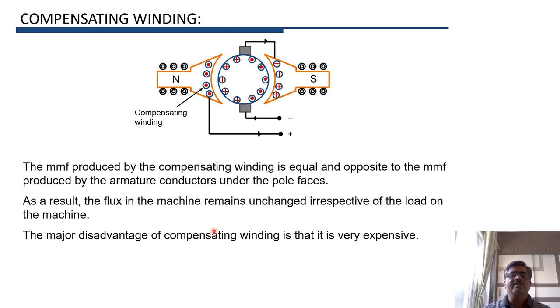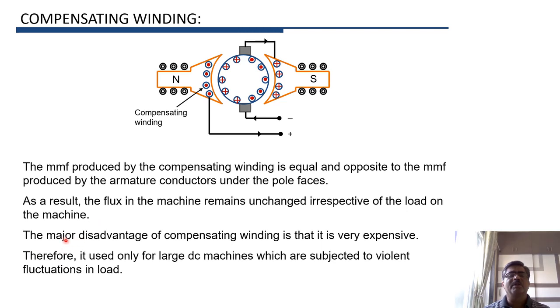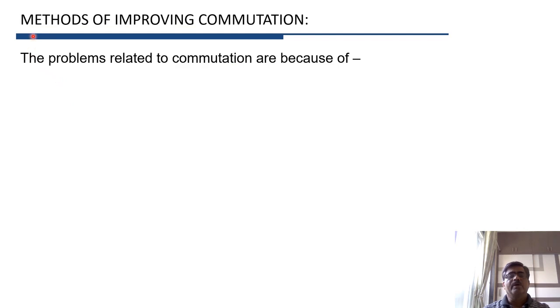The main disadvantage of compensating winding is that it is very expensive and takes up a lot of space in the machine. Therefore compensating winding is not normally used in small machines, but is normally used in large DC machines particularly if the machine is subjected to violent fluctuations in load. However, the compensating winding can neutralize the demagnetization effect but it cannot neutralize the cross-magnetizing effect.